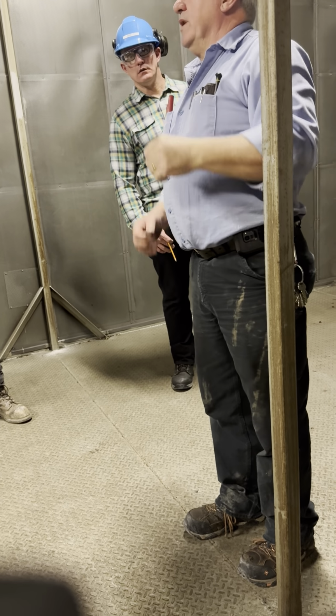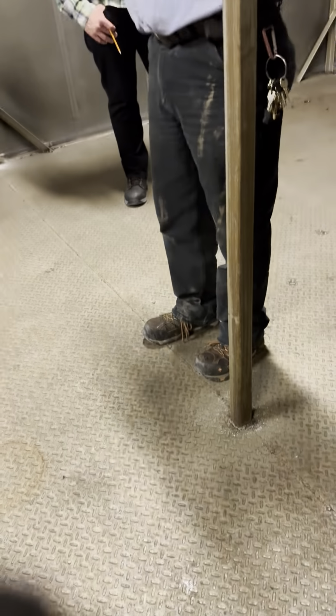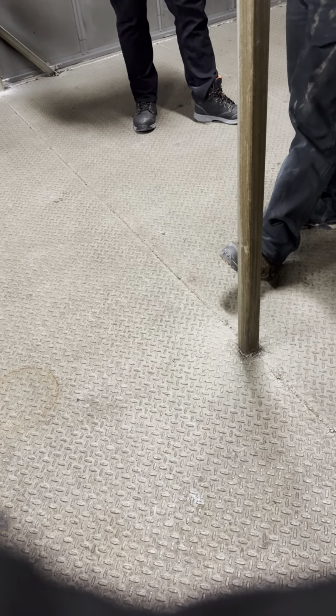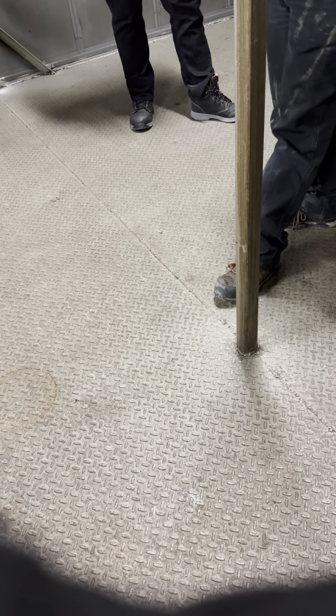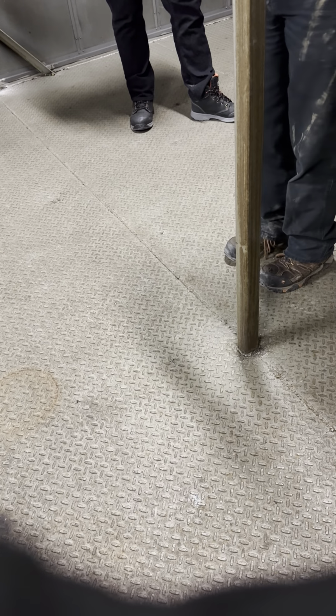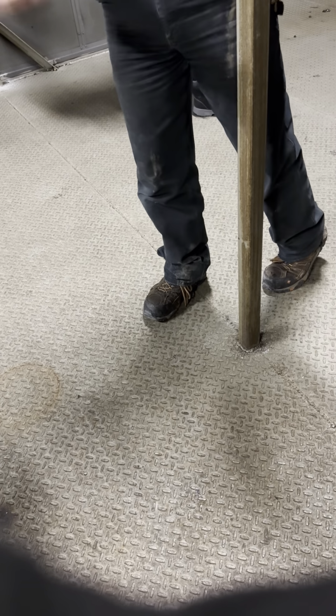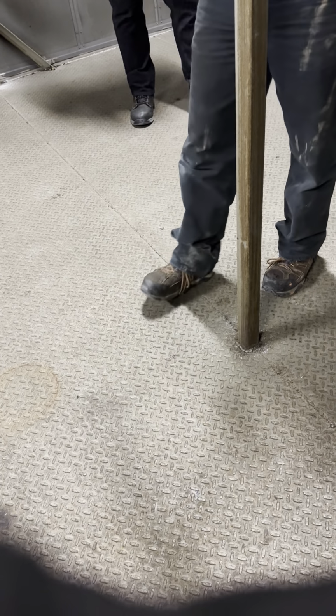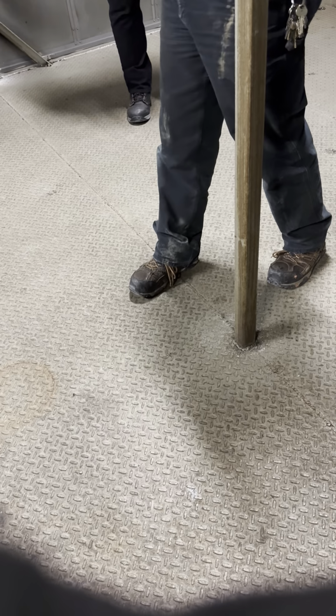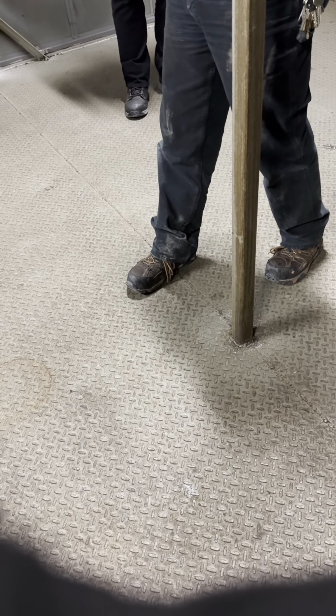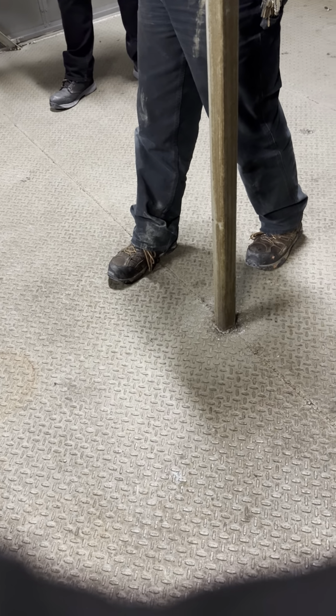So we had one air handling unit which was on the roof. It wasn't a small one, it was a nice size one, not too big, a bit smaller than this room. We had a door right here, and the freeze alarm was tripping around the coil. I would open up the door because it had tripped, and that's the other thing: once an air handling unit is tripped, your heating should go to 100%, even during the summer.